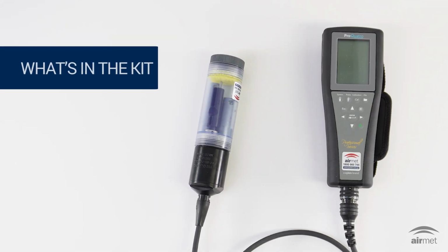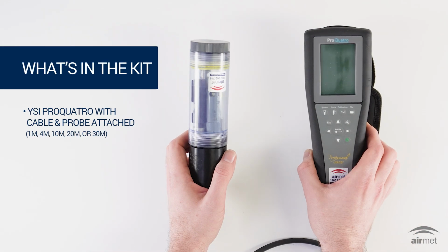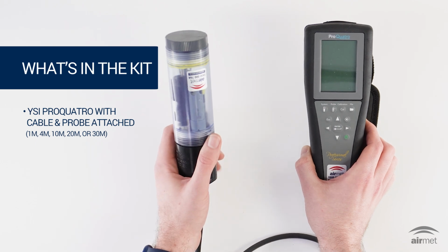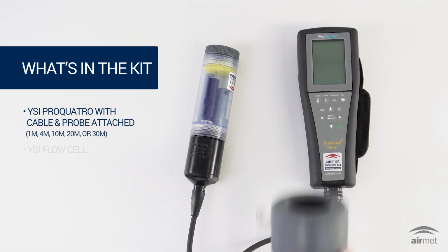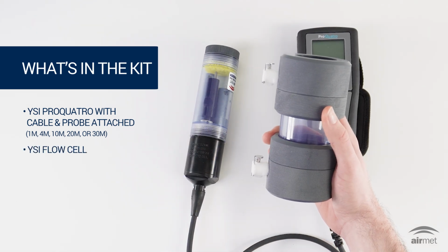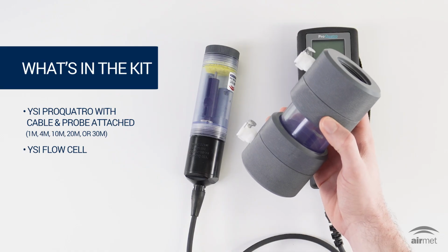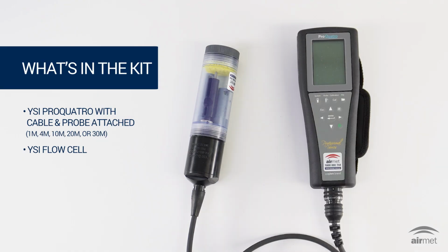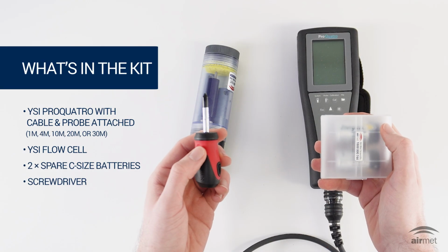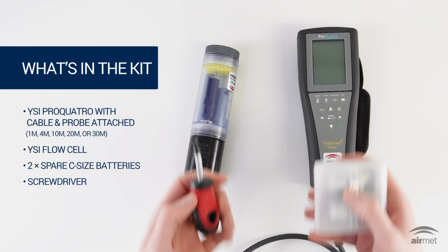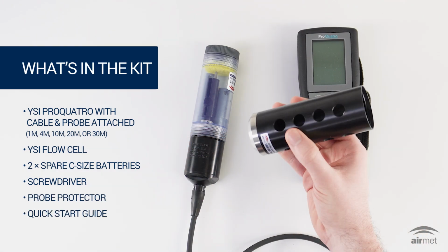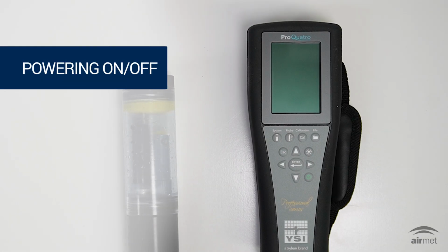When hiring the YSI ProQuatro from AirMet Scientific, the unit will include the YSI ProQuatro unit with probe and attached cable, a YSI flow cell, which allows for controlled sampling of the environment by reducing disturbance and degassing, 2 spare C-size batteries and a screwdriver to replace the internal batteries, and a probe protector for when the flow cell is not used. To begin, let's look at powering the unit on and off.